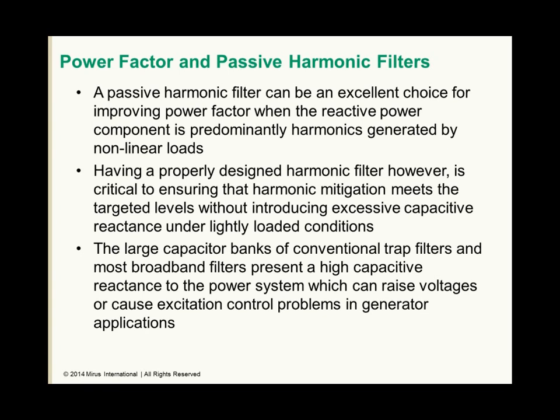Having a properly designed harmonic filter, however, is critical to ensuring that harmonic mitigation meets the targeted levels without introducing excessive capacitive reactance under lightly loaded conditions. The large capacitor banks of conventional trap filters and most broadband filters present a high capacitive reactance to the power system, which can raise voltages or cause excitation control problems in generator applications.